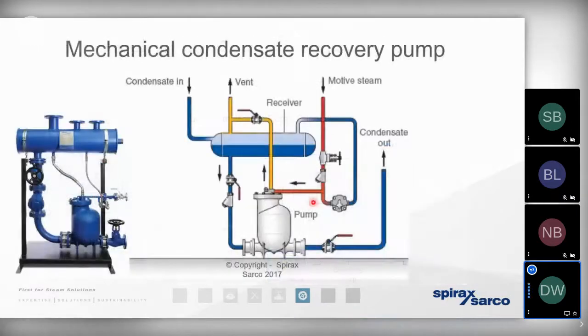And of course, we can also use a mechanical condensate recovery pump. It's essentially the big brother of that automatic pump trap. We're using the motive energy in the steam to pressurize the liquid condensate and shunt the condensate back mechanically. We don't need any electrical installation. And because of that, we're not at risk of any pumps cavitating or failing.